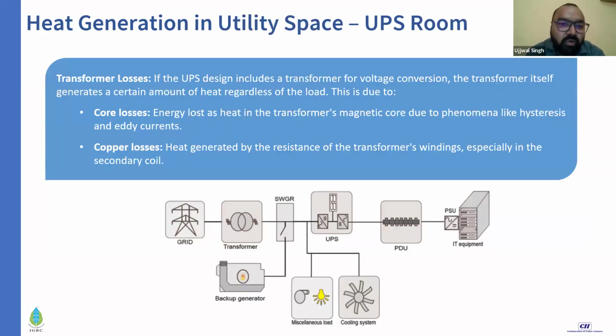Now, moving from your white space to your UPS room. Why we need to calculate heat loads in the UPS room is that the UPS room, just like your white space, is a controlled environment, and failure of cooling in your UPS room will eventually lead to failure of the UPS, and that will be a failure of all the power going to your IT devices. So it is as important as the IT room when it comes to cooling infrastructure.